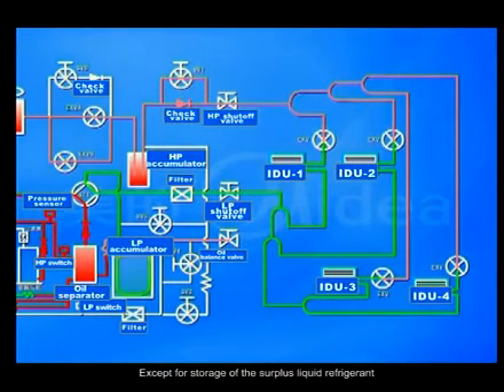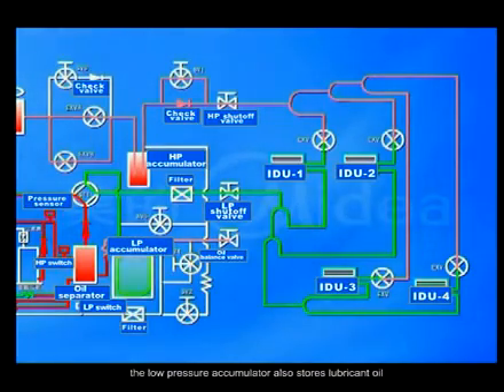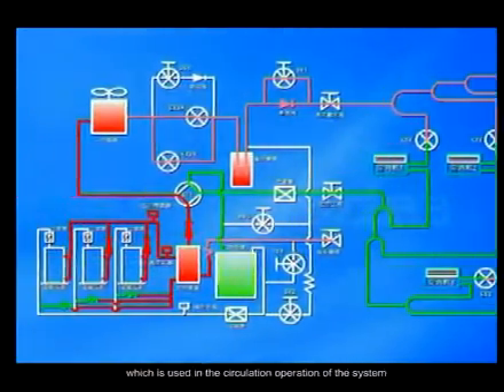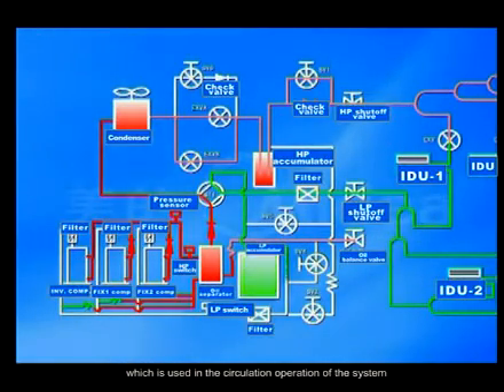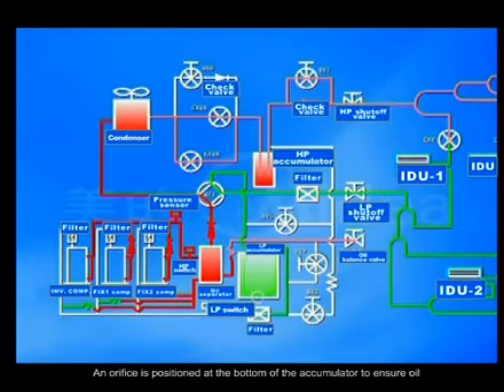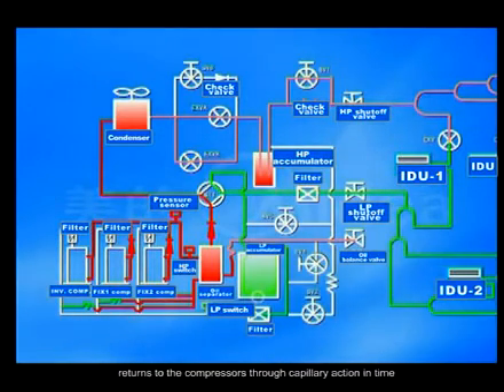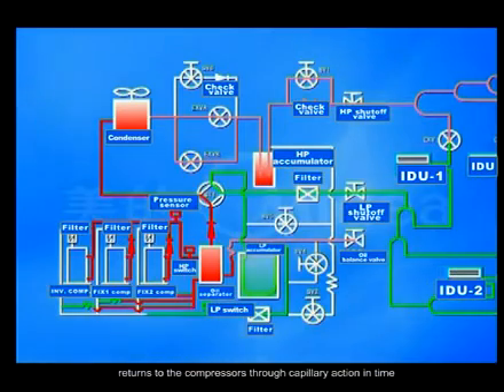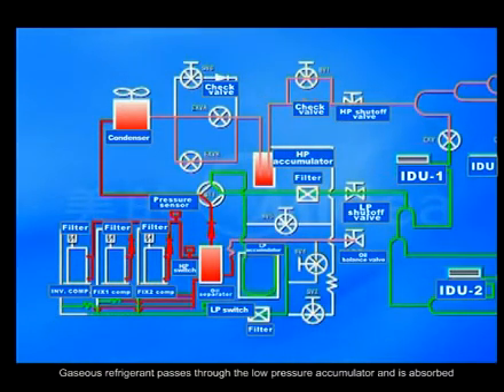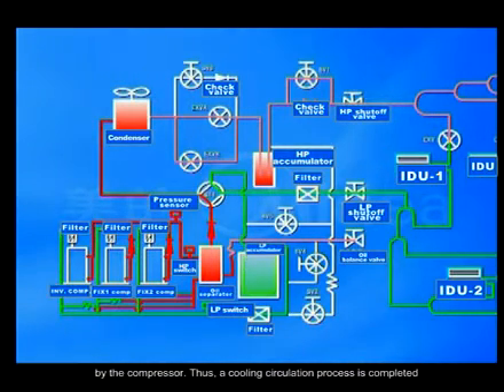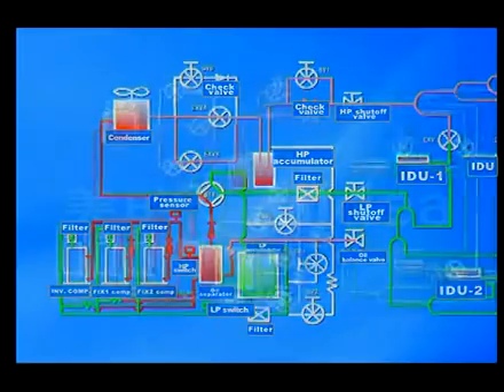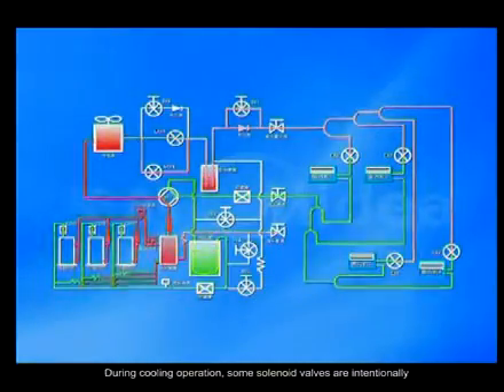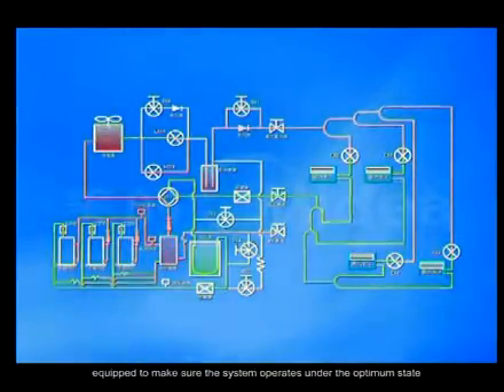Except for storage of the surplus liquid refrigerant, the low-pressure accumulator also stores lubricant oil, which is used in the circulation operation of the system. An orifice is positioned at the bottom of the accumulator to ensure oil returns to the compressors through capillary action in time. Gaseous refrigerant passes through the low-pressure accumulator and is absorbed by the compressor. Thus, a cooling circulation process is completed. During cooling operation, some solenoid valves are intentionally equipped to make sure the system operates under the optimum state.